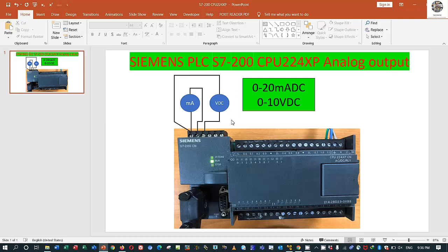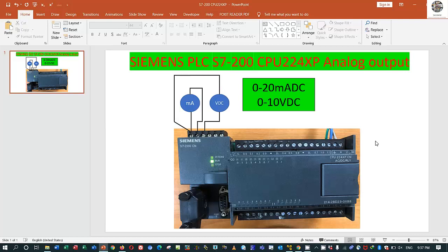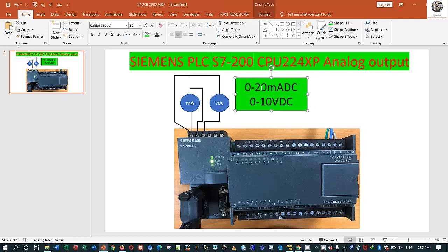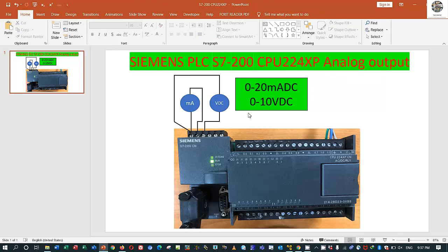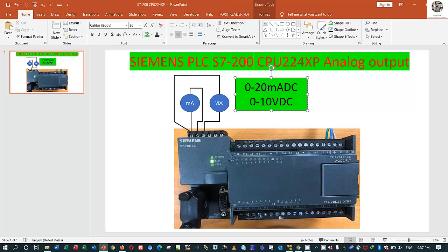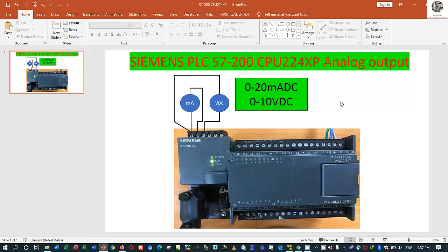Normally if we bought the PLC CPU 224 without XP, it means that we don't have the built-in analog output. But when we bought the PLC 224XP, we will get the analog output card that's built inside the CPU. The range of the analog output comes from 0 to 20 milliamp and 0 to 10 volt.